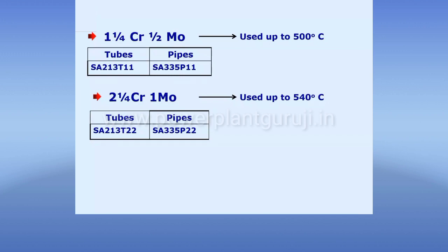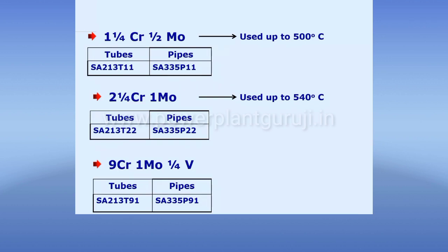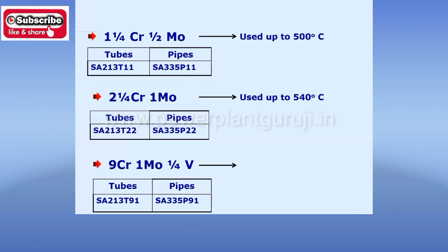This is a modern metallurgy — for the last 15–20 years it has been in use — and that is T91 metallurgy, which is 9% chrome, 1% moly, and 0.25% vanadium added to increase its creep resistance. It is a highly creep-resistant steel. SA213T91 for tubes and SA335P91 for the header. Your main steam header will be of P91 metallurgy for 500 MW, 660 MW, and 800 MW units. In a 660 MW unit, the final temperature is in the range of around 570–580 degrees centigrade.